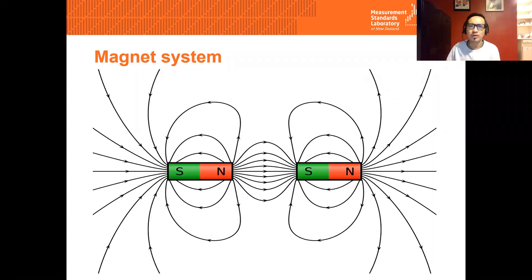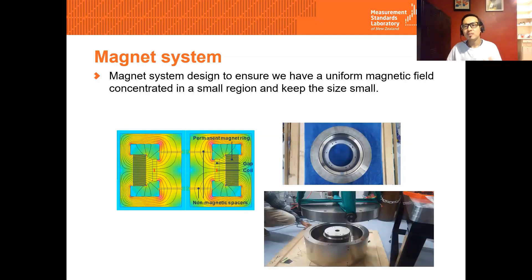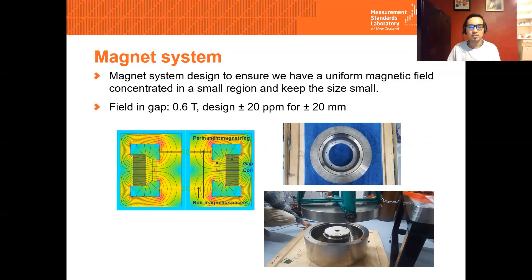One of the critical requirements for a Kibble Balance is to have a strong and highly uniform magnetic field where the coil moves through. The easiest way is to have big magnets, but that would not be practical — too big and too expensive. Instead, we can make a magnet system consisting of a ring permanent magnet and a yoke of soft magnetic material, put them together to create a magnetic circuit with highly uniform magnetic field at the coil region. Our magnetic field strength is 0.6 tesla and has high uniformity. Having the magnet entirely enclosed by the yoke also screens the magnetic circuit from outside magnetic interference.